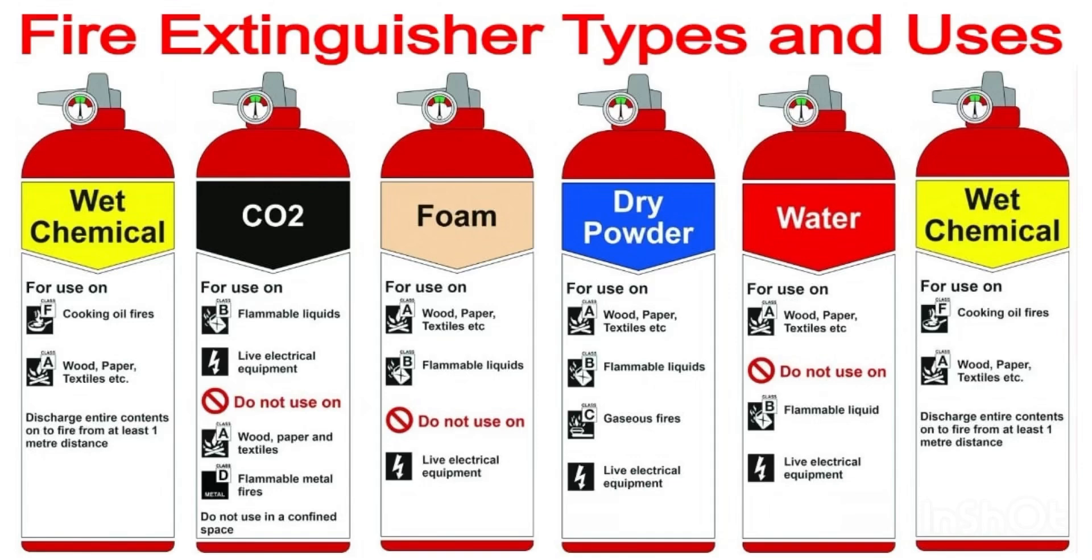Second, carbon dioxide type for use on class B fire and class E fire. Class B is flammable liquids. Class E is electrical fire like short circuits. Remember, do not use on class A fire or class D fire: wood, paper, textile and flammable metal fire because this is CO2.